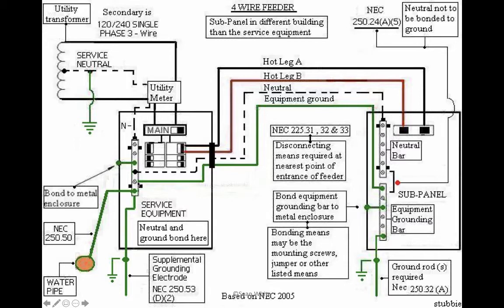Here's an equipment grounding conductor that's going to the sub panel, right there, and we only have a single point of system grounding here. We don't have a point of system grounding there in the sub panel, because if we did, that would be a ground fault, because some of the currents that would otherwise be going down the neutral would have an alternate pathway down this equipment ground, and that's a no-no. Equipment grounds are not supposed to carry current.